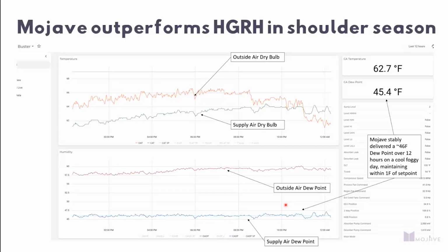Now, a good example of that would be we actually excel in situations where it's part load, and even in situations where traditionally hot gas reheat DOAS struggles. So days where it's very high humidity content, but not a great or large cooling load. So cool, foggy, rainy day where it's 65 degrees and a lot of rain outside and a lot of humidity or moisture outside. Traditional hot gas reheat DOAS struggles because it has to overcool the air to dehumidify and then bring that air back up to neutral with hot gas reheat. With our product not requiring overcooling to dehumidify, we're able to really maintain steady dew points where traditional DOAS products cannot.